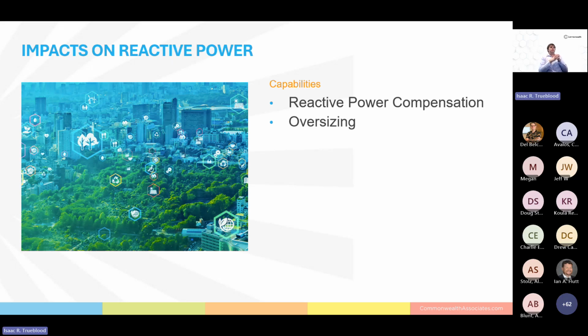Next, I'll talk briefly about reactive power. This partially connects back into the impacts on voltage. Distributed energy resources need to be capable of maintaining acceptable voltage conditions for the distribution systems. This means providing or consuming reactive power to maintain acceptable voltages. Luckily, most rotating machines are capable of providing that reactive power without much concern. However, inverter-based distributed energy resources, which is what I have mostly experienced, need to have extra care put into their design to ensure they can produce these acceptable amounts of reactive power.